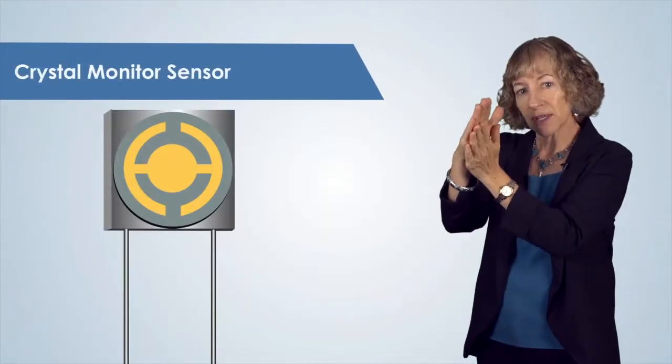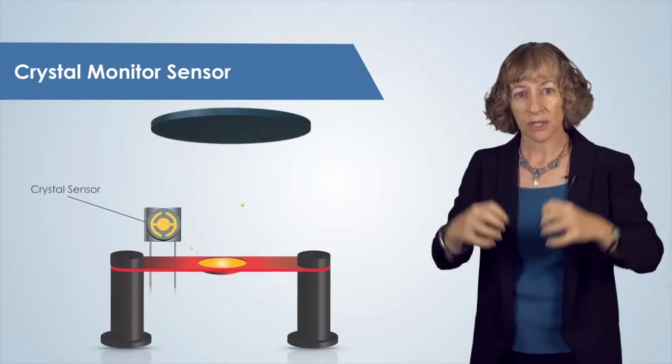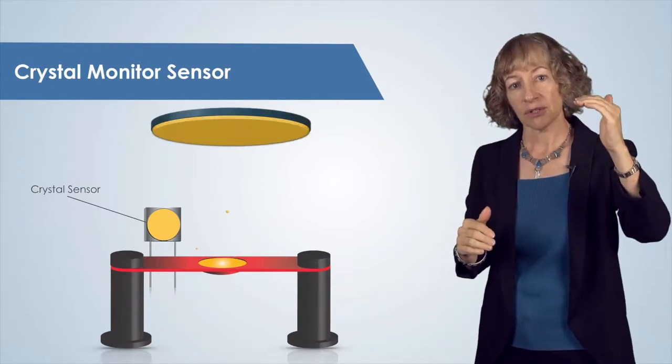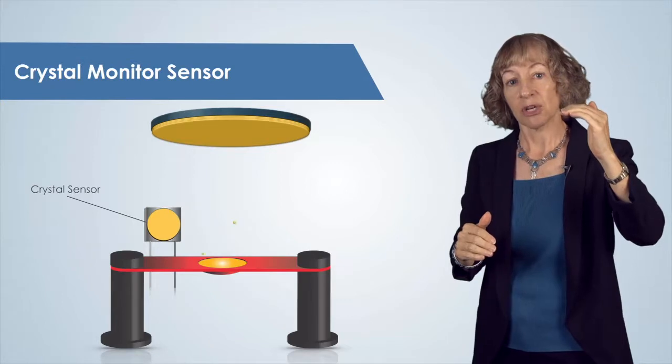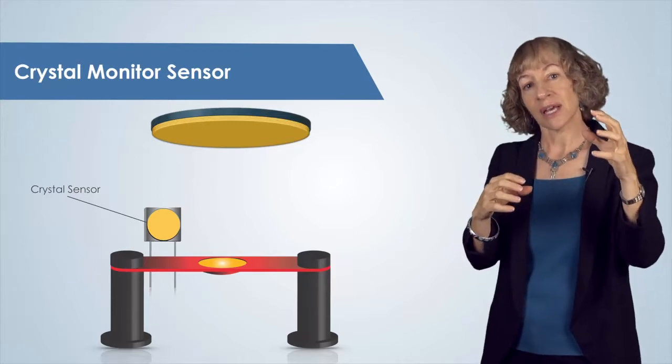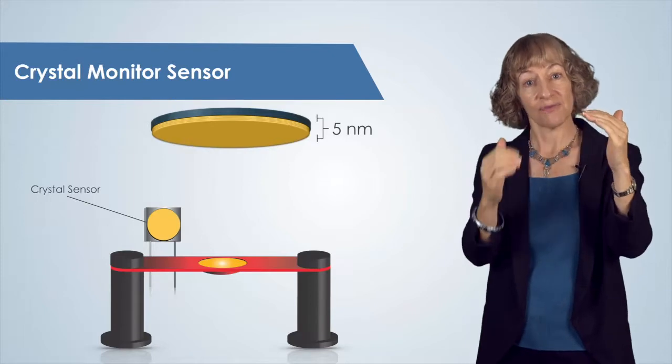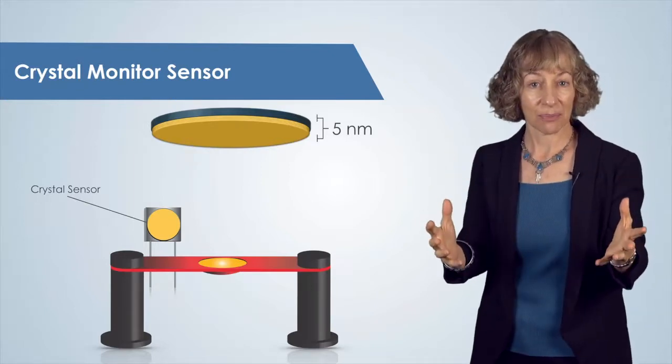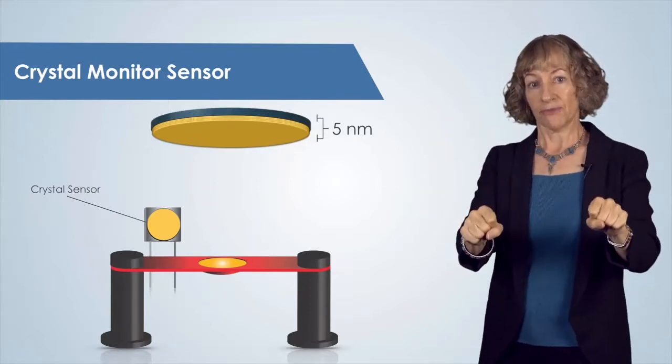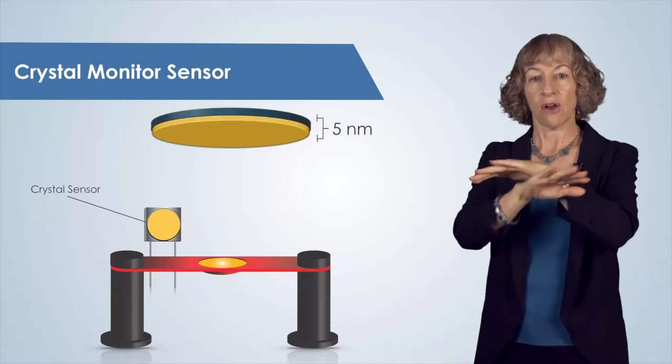To monitor this film thickness, we place a crystal sensor in the vacuum chamber, so that the source material is deposited onto the sensor at the same rate as onto our substrate. This crystal sensor vibrates, and the vibration frequency changes as the film is deposited onto the crystal, enabling us to sense this change in vibration and calculate that deposited film thickness as the deposition is taking place in real time. When the desired thickness is reached, we stop the flow of electrical current through the boat, which stops the heating of the source and halts the deposition.